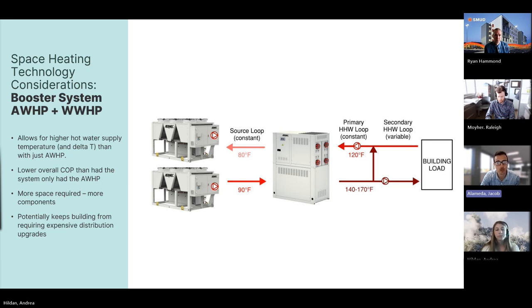But if you don't have a source, you can actually, in a way, create your own source to allow you to get a higher heating water temperature for your building. So this strategy is starting to be known as a cascade system or a booster system. On the screen here, it's just a simple diagram of what this looks like. On the left, you have air-to-water heat pumps operating at a very efficient condition to create your water source. And then you have water source heat pumps that generate your building's actual heating hot water temperature at 165 degrees.